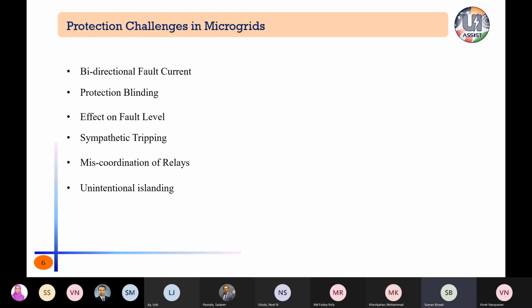So from a protection perspective, some of the major challenges are highlighted here. That is bidirectional fault current. This is due to the fact that when DGs are integrated, DGs start contributing towards the fault location, so the direction of fault current changes. This necessitates the incorporation of directional relays in the lines, which increases the cost of the system. The second one is protection blinding. This comes because we are integrating DGs at various locations, or as we can say at various buses of the distribution system, and it reduces the current drawn from the substation.